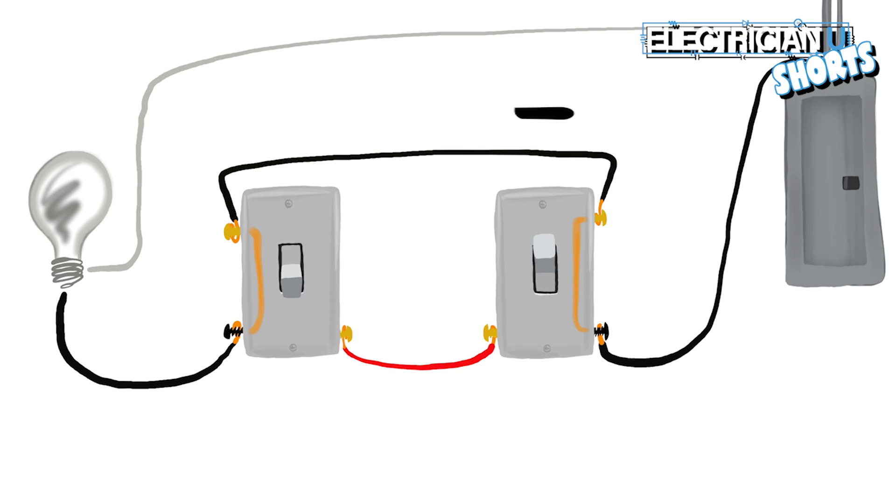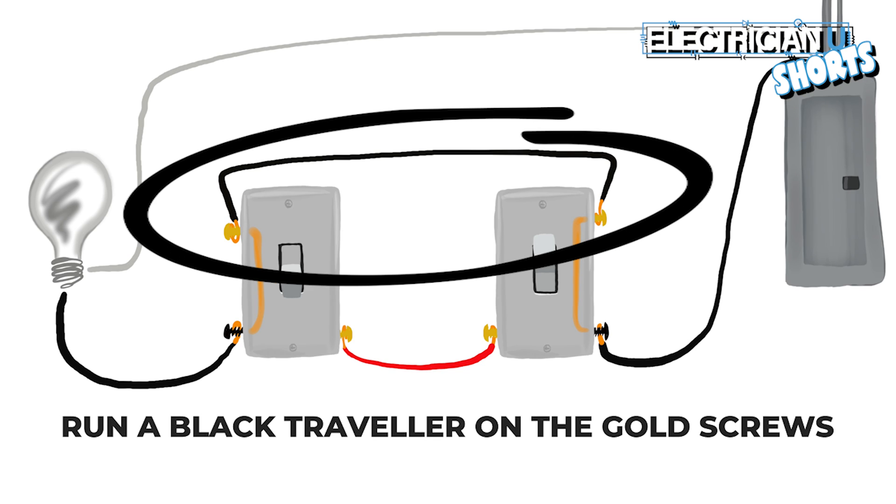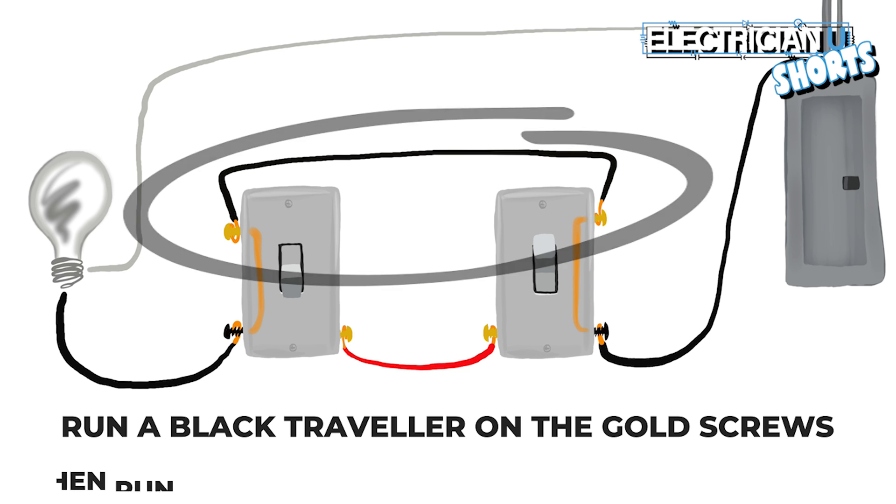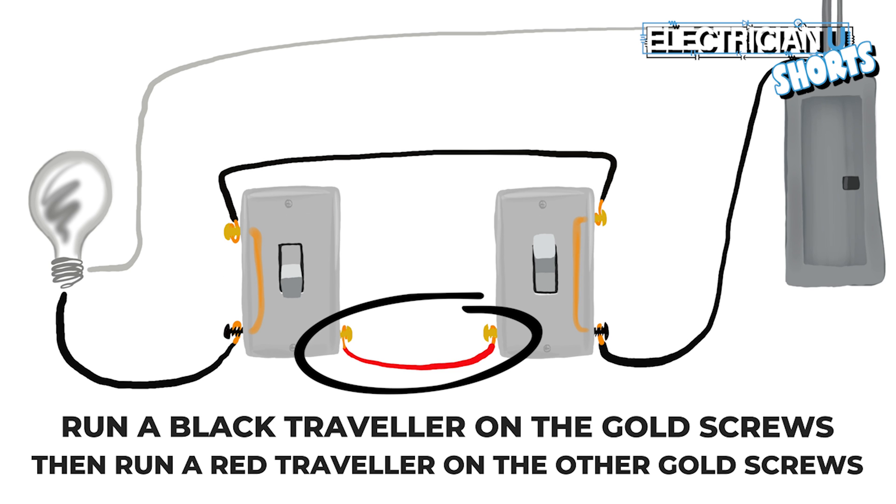So we've got one traveler that you would run from this device to this device and we'll call this your black. In a 12-3, the travelers that you're going to run, you're going to run one black conductor and you're going to run one red conductor.